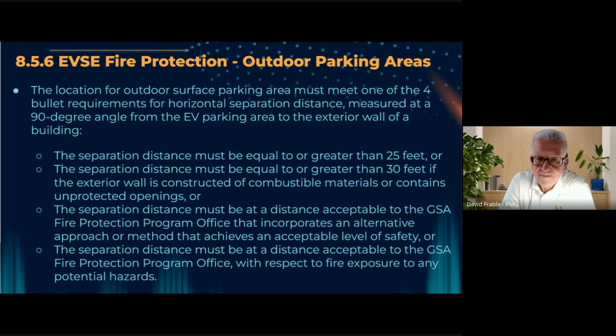Option one is the separation distance, at least 25 feet or more. Option two is the separation distance, at least 30 feet or more if the exterior wall of the building is constructed of combustible materials or contains unprotected openings.